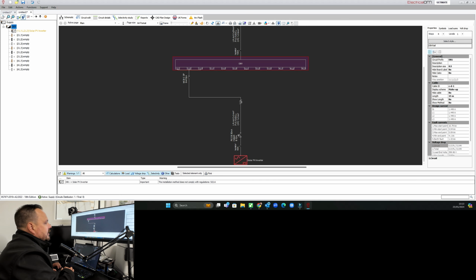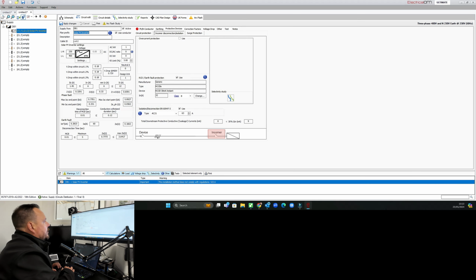Now again, with this final circuit for the solar PV, you can see we've got a few things already pre-selected there, but we'll start by giving it a description. So we'll call this GivEnergy, for example, 11 kilowatt, and we'll just call it three phase. So now we can set our rating on that. You see we've got the AC kilowatt value. So if we put that to 11 kilowatts, and we can also size the PV array on there as well, but we'll get to that when we pop the string details in. For the minute, we're going to concentrate on this.